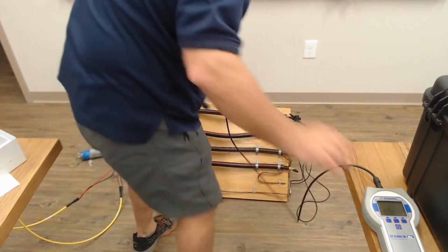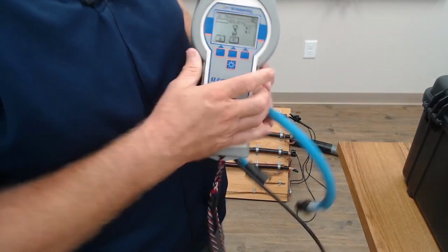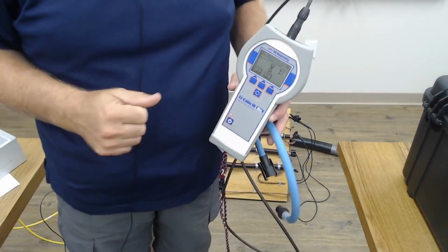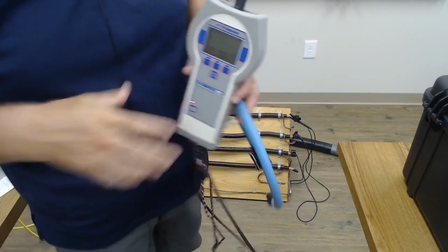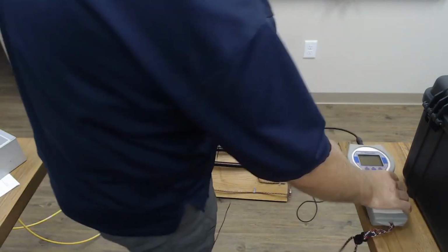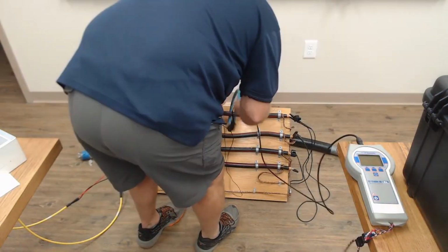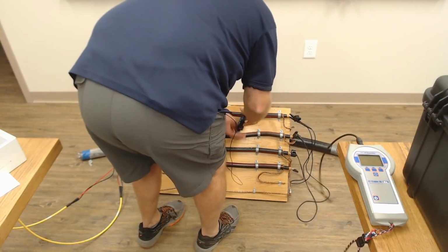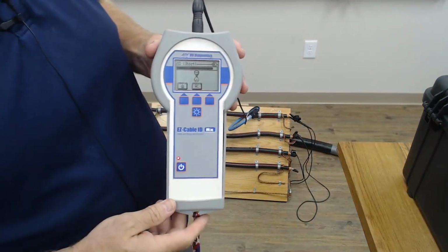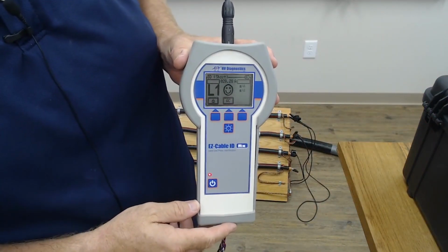Now, we would take this off, leave our known reference point on the cable, and now we would walk down the cable to the manhole or wherever we have access to the cable. Once we get to that point, we'll put this on and say, hey, what is this? And it should come back with an L1 smiley face. And there we have it.